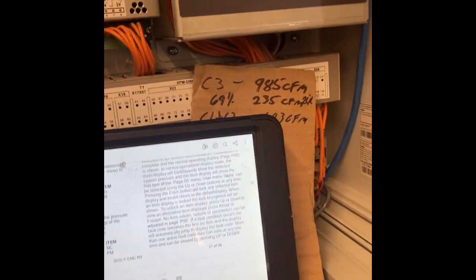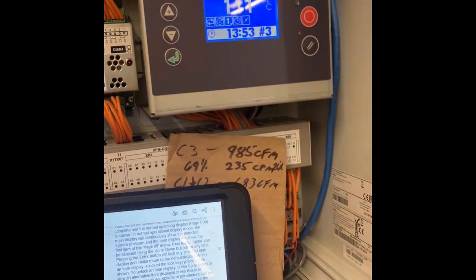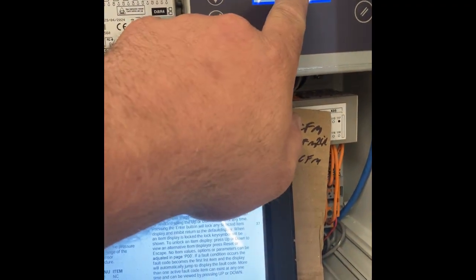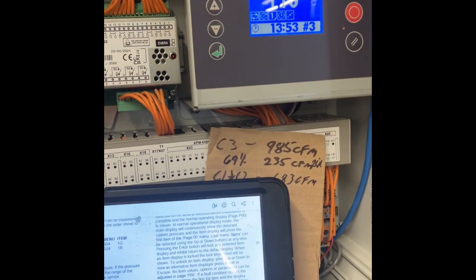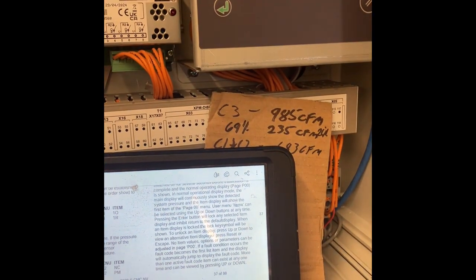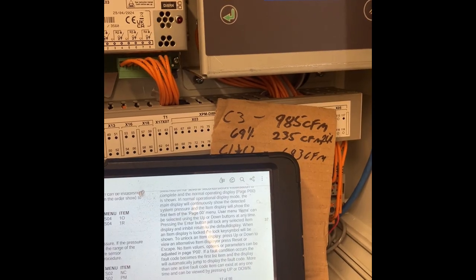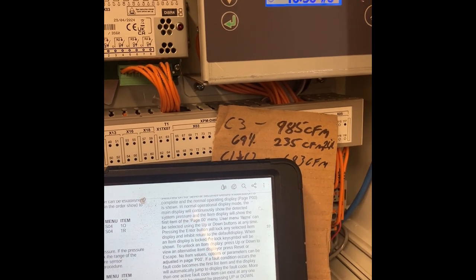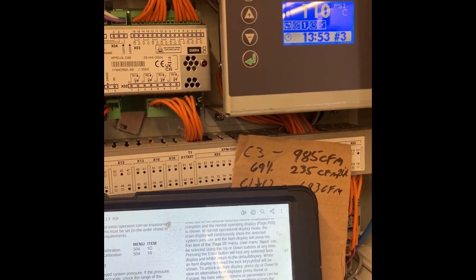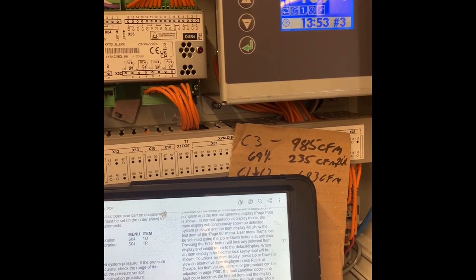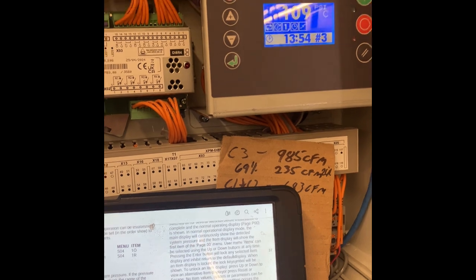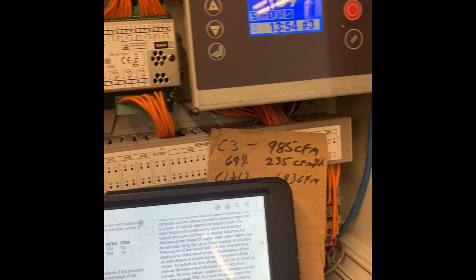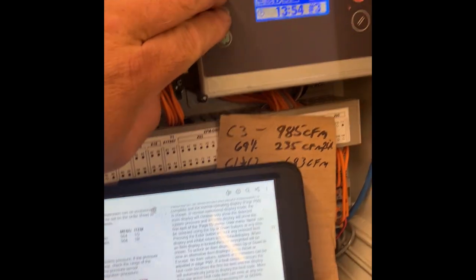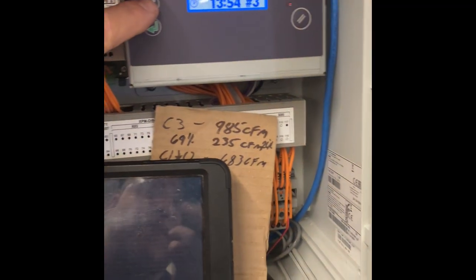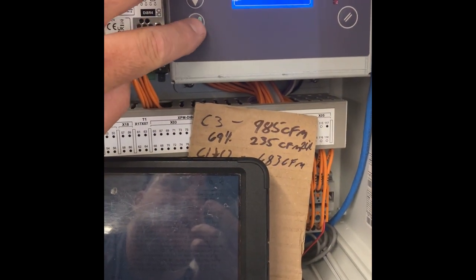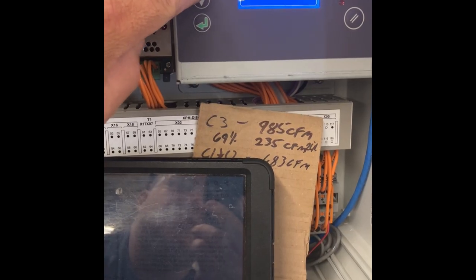First things first, when you fire this thing up, you should be getting a pressure reading. If you're not getting a pressure reading, check your sensor wiring, you've got something going on there. You'll see from the earlier video I kind of biffed the sensor wiring because I wasn't paying attention to the wiring diagram in here, but got that fixed though. So now we're reading. What we're going to do is hit plus and minus together - that's a horrible glare - hit plus and minus together, and we're going to put in password 32.